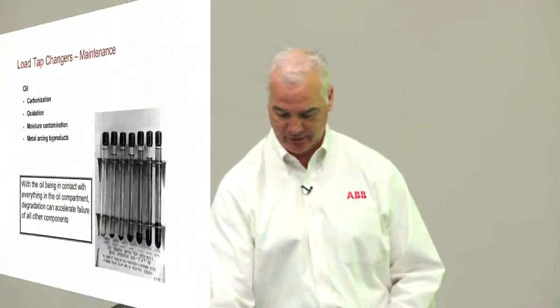You don't want to open it up and close it back up, because you have tolerances on how tight you tighten the hardware, and without replacing that gasket, you'll probably end up with a leak after you do that. So you want to make sure you do that. Also, there's some weld seams and paint finish. You should verify those as well. Basically, the welding is typically like you would on any tank. You're just verifying that there's no leaks or anything on the tank when you're doing your maintenance cycle.